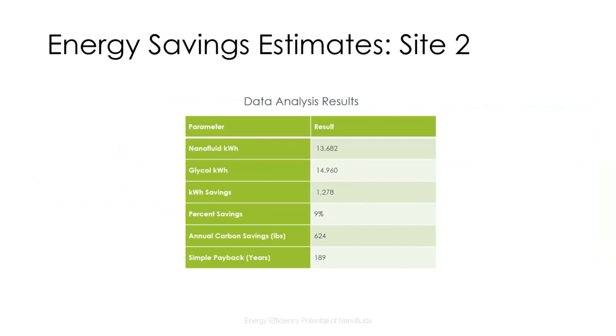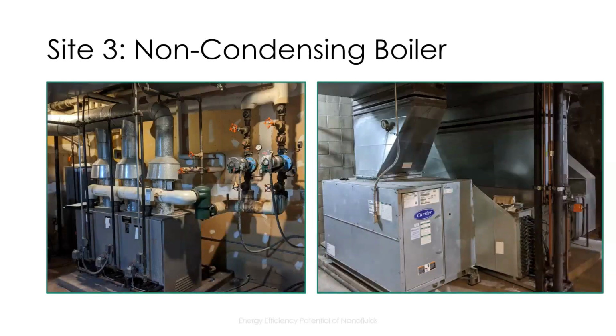Okay, as seen from this table, our data analysis resulted in positive energy savings in this case, consistent with the gain in efficiency shown on the previous graphs. As mentioned, the calculated loading was relatively low in a similar fashion to the water-cooled chiller. So if you were to apply the equivalent full load hour loads from the Minnesota Technical Reference Manual, you'd get about 4 times the energy savings shown on this slide.